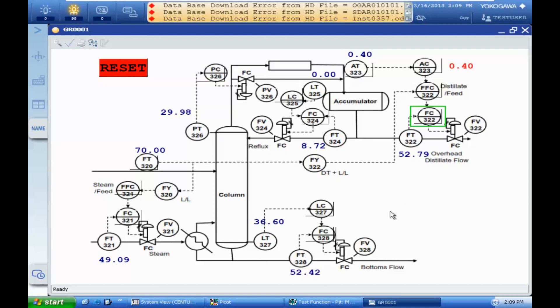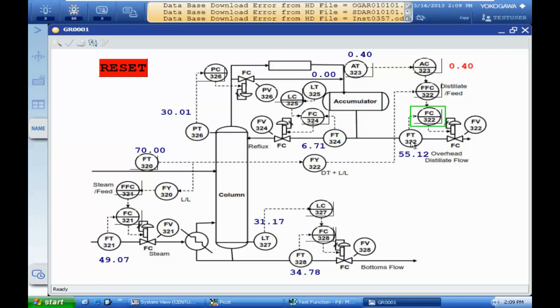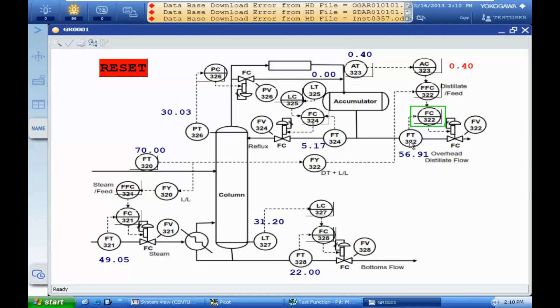You can see that the set point is 63 and the level of the column is decreasing dramatically in order to keep the balance. We are reaching the set value very quickly, the level is decreasing, and we are getting close to normal operation. The set value here is 63.